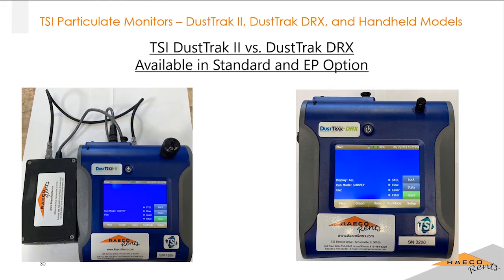And any of those things can cause problems with your readings. But as far as having tubing hooked up to it, it's not the most common. The only time that we see that is especially in our environmental enclosures. Basically, you've got a big case that houses the DustTrak and some big external batteries. These are the things that go on those construction jobs for a long time, and those need to be in weatherproof cases. And there's non-conductive tubing. That's the important part. Non-conductive tubing runs from the DustTrak to the inlet, where the DustTrak is going to be pulling air through the case. And that helps to make sure that all this dust doesn't accumulate on the tubing too much.